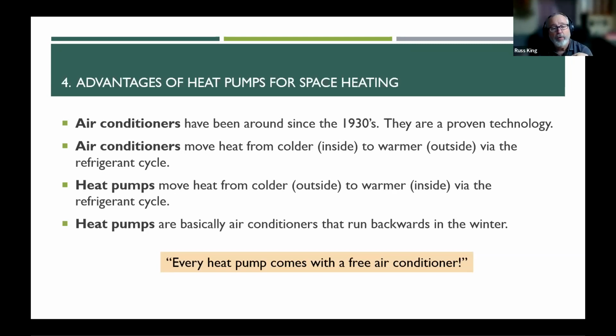Air conditioners move heat from colder to warmer via a refrigerant cycle. Heat pumps move heat from colder to warmer via a refrigerant cycle. It's the exact same technology. Heat pumps are basically air conditioners that run backwards in the wintertime. They have a reversing valve, and they just click over and run backwards. And this is a great quote: every heat pump comes with free air conditioning. So if you're going to put a heat pump on your house, guess what? It comes with free air conditioning. All right, so the technology's fine. Don't worry about the technology.